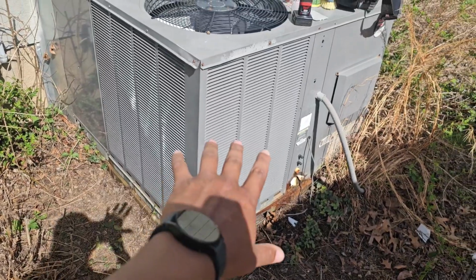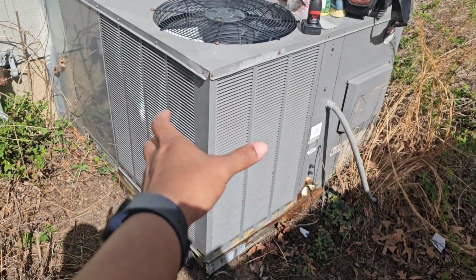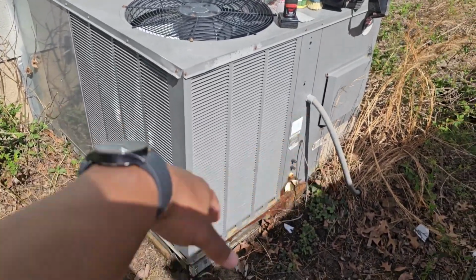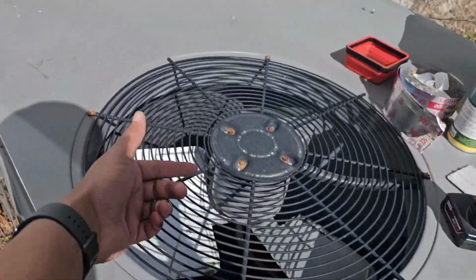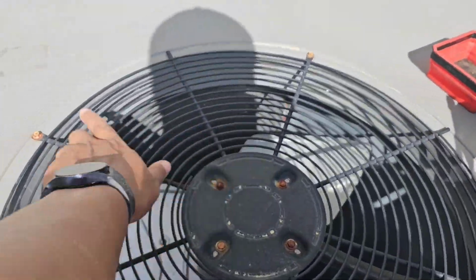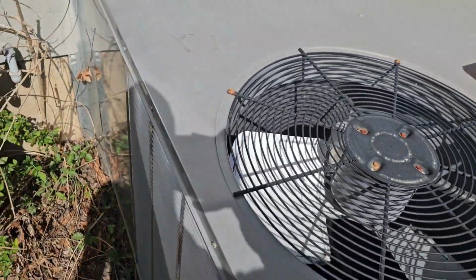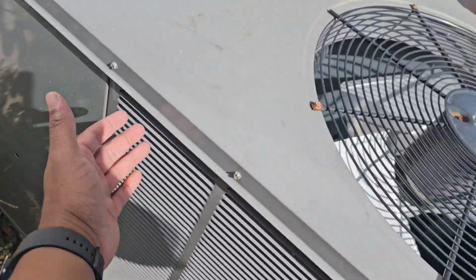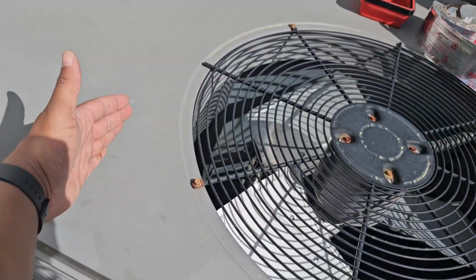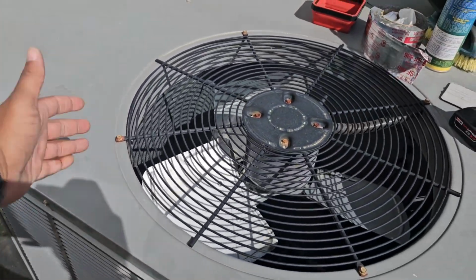I took off the entire panel for the condenser coil, cleaned off these two sides as best as possible, removed the top, and sprayed down the back end a little bit. It wasn't really noticeable viewing it from this side. This side of the coil on these Rheem rooftop package units are always the dirtiest.